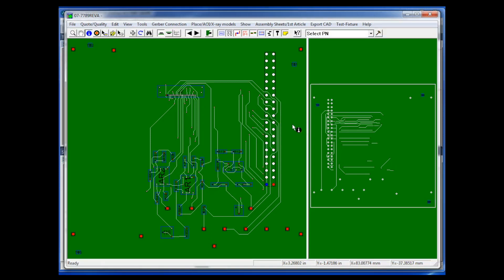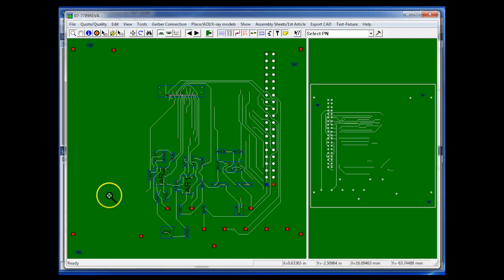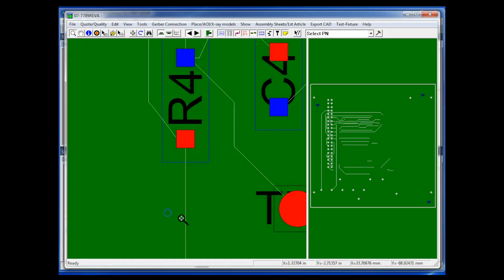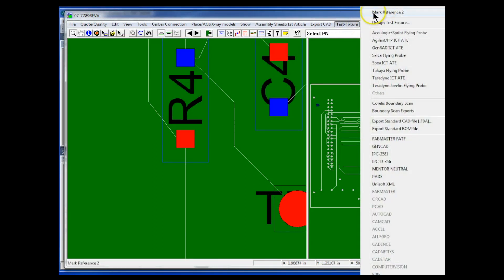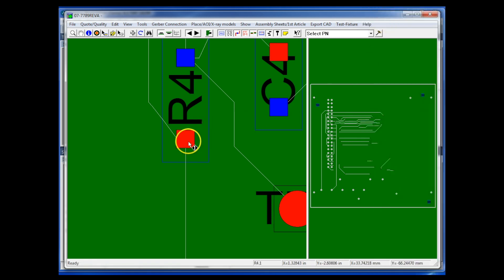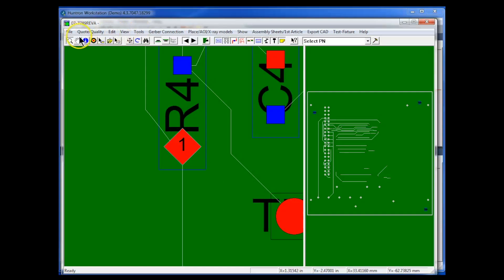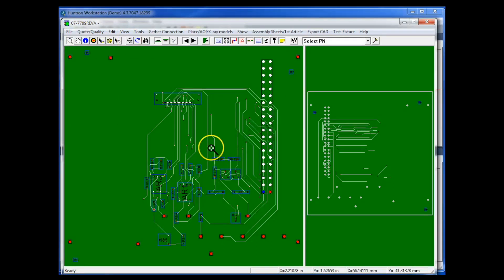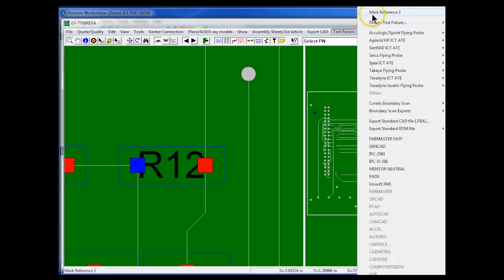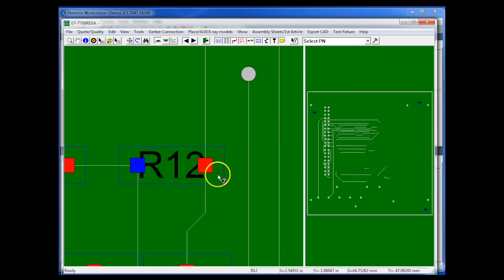The next step is to select two alignment points used by the Access Prober for positioning the board within the prober area. We'll select those points here in ProntoView Markup. Zoom in on a point for the first alignment — I'll select a pin on U4. Go to the Test Fixture menu and select Mark Reference 1. Then zoom out, select another point, go to Test Fixture menu, select Mark Reference 2, and click on the right side pin of R12 as our second alignment point.